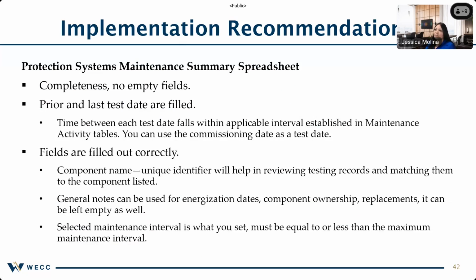The general notes can be used for energization dates, component ownerships, replacements, and can be left blank as well. This should be the only field that could be left blank. And your selected maintenance interval is what you set as an entity, and it must be equal to or less than the maximum maintenance intervals listed in the standard.